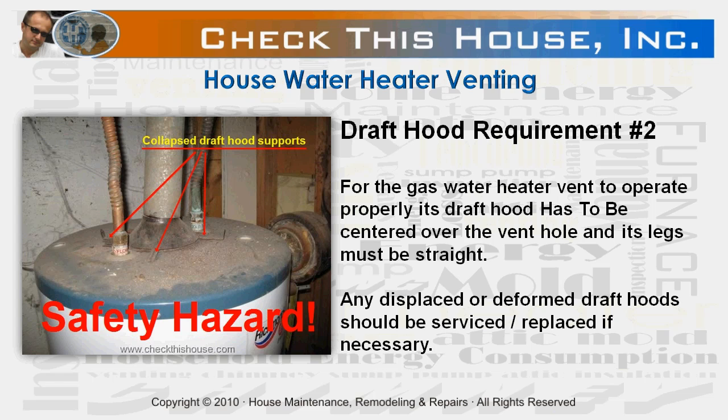Draft hood requirement number two: notice on the picture how the draft hood has collapsed on its legs. This happened because the draft hood wasn't properly secured and it was supporting the entire vent pipe weight at the same time. Therefore, remember that for the gas water heater vent to operate properly, its draft hood has to be centered over the vent hole and its legs must be straight. Any displaced or deformed draft hood should be serviced and replaced if necessary.